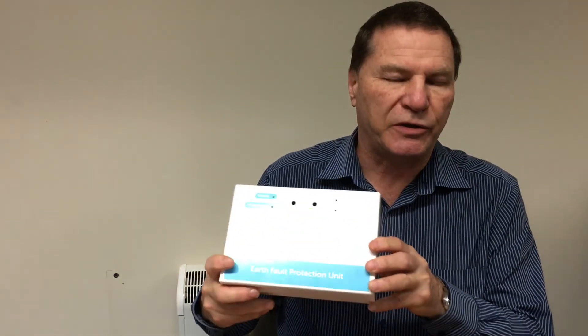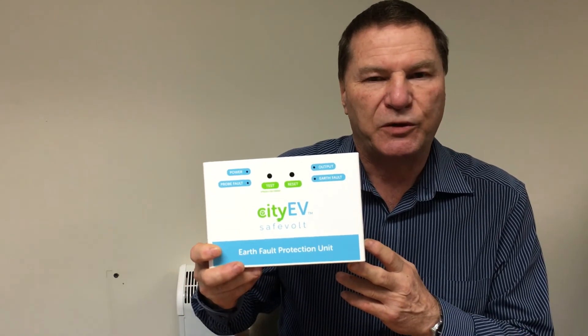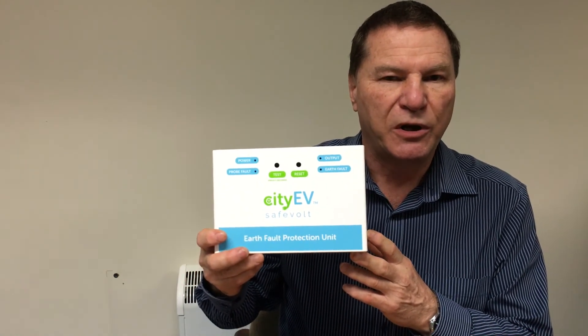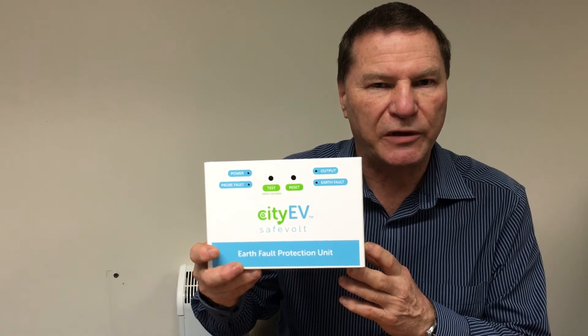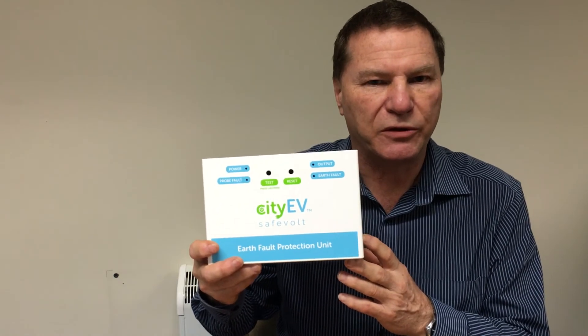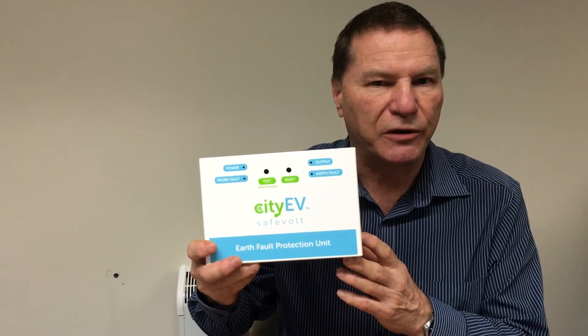Type B RCDs have the disadvantage that they are very expensive compared to standard Type A RCDs — in many cases several hundreds of pounds. In addition to the PME protection, the CityEV SafeVolt also incorporates Type B RCD functionality, meaning it will trip if it senses a DC leakage current of greater than 6 milliamps. This represents a considerable saving on EV installation costs, as only a standard Type A RCD is then needed to protect the EV circuit.